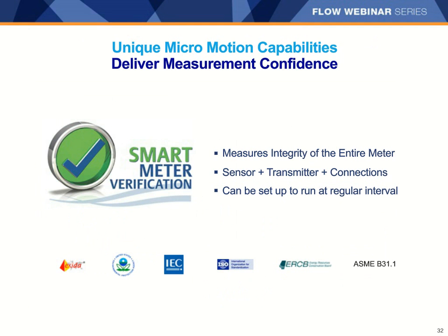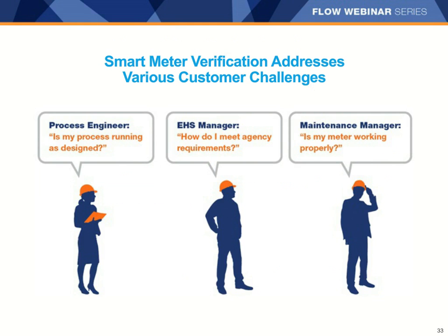Even with Coriolis's measurement stability, sometimes when a measurement is important, such as for fiscal custody transfer, safety, or critical process control, you want the confidence to know your flow measurement is reading correct. Emerson is focused on delivering that with Smart Meter Verification. There are various people in the plant that interface with our flow meters, from maintenance and engineering to environmental health and safety personnel. Many different areas of the plant can benefit from Smart Meter Verification. At this point, I would like to show a short video on what SMV is and its potential benefits within your plant.